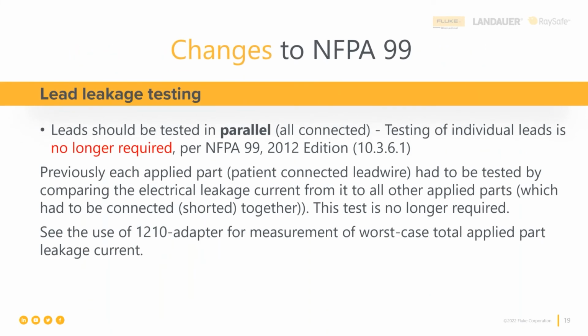Okay, so what changed in NFPA 99 since beginning in 2012? Lead leakage testing. So this would be lead to all other leads. Leads should be tested in parallel, all connected. The testing of individual leads is no longer required. You can short together all of the continuously conductive patient connections and test them as one test lead.